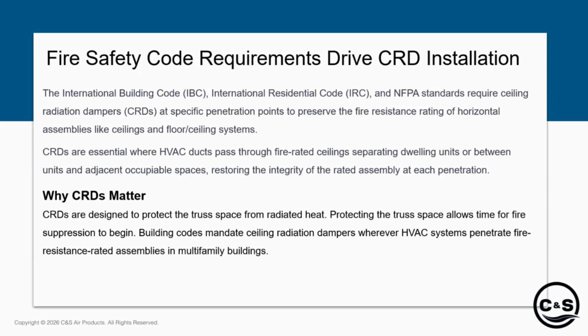So CRDs are basically there to make sure that the radiated heat from the space below, in the case of a fire, actually doesn't self-combust the truss space above. So that's why radiation dampers are installed in every single building when it comes to multifamily construction. So do you have anything to add here, Brent?